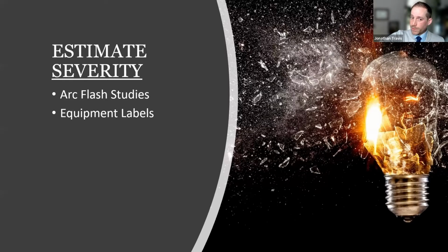The arc flash one's a little bit trickier to figure out, our threshold for that. Now, I mentioned 1.2 calories per centimeter squared. A lot of people will use that, and arguably you can look at the standards and that's what it'll tell you to do. Personally, what I look for is, can there be an arc flash at all from this piece of equipment? Because even if it was 1.1, I still wouldn't want to be standing there, because you're dealing with, like I said, heat energy, but there's a fireball, there's a blinding light, there's loud sound, there's molten shrapnel. Maybe you don't receive a second degree burn from the heat energy, but if you're not wearing PPE, your clothes are on fire.